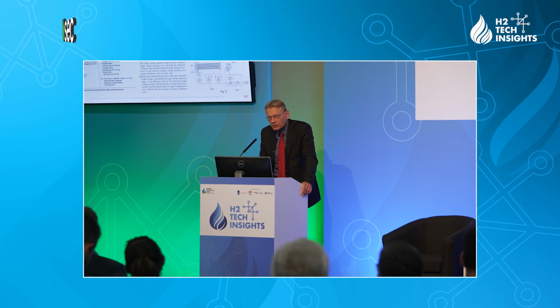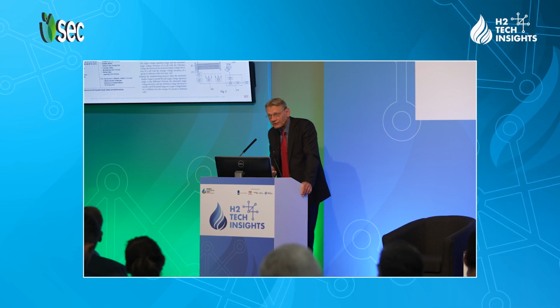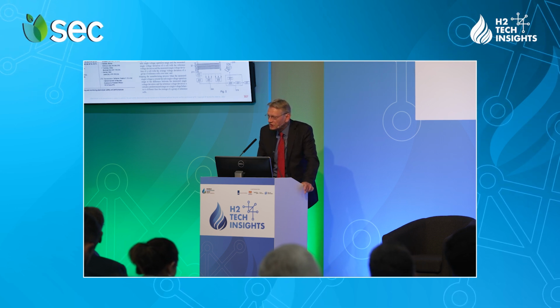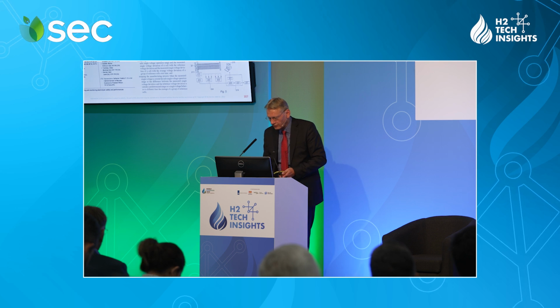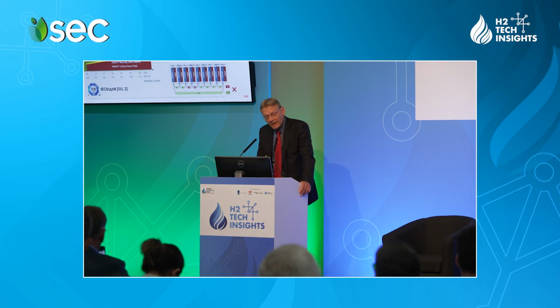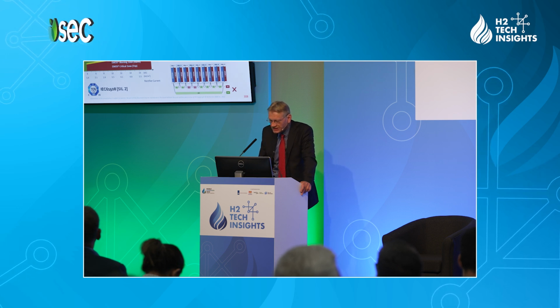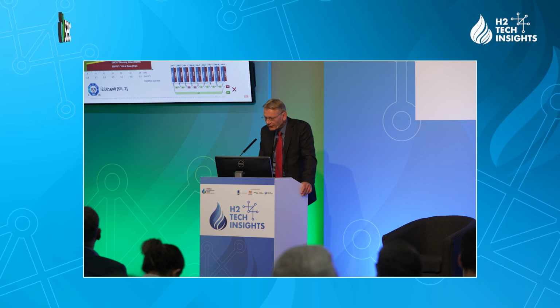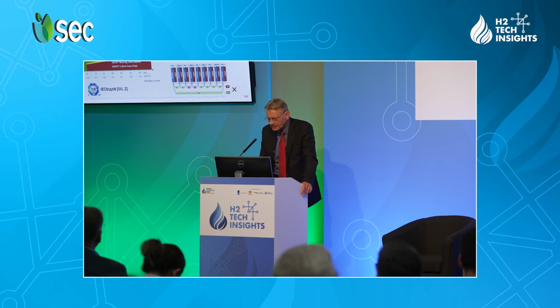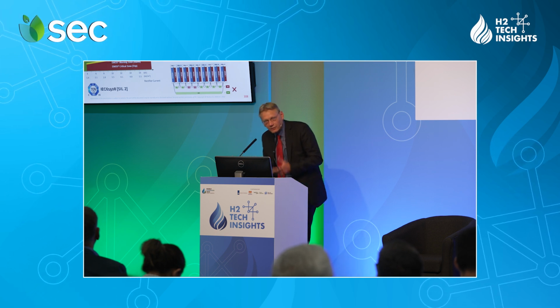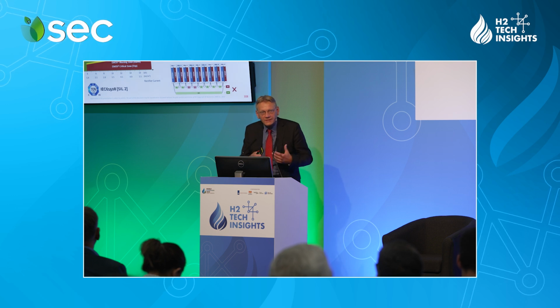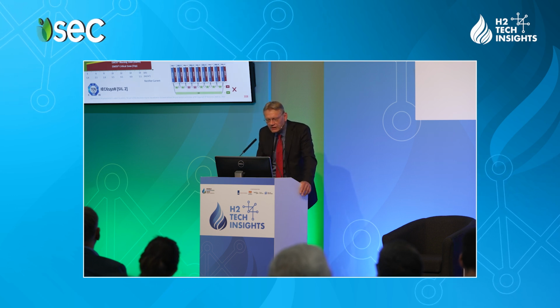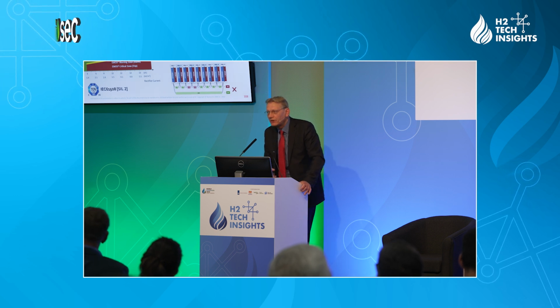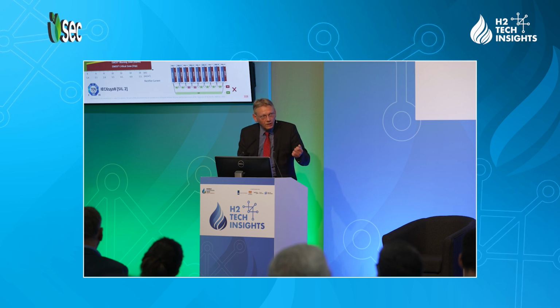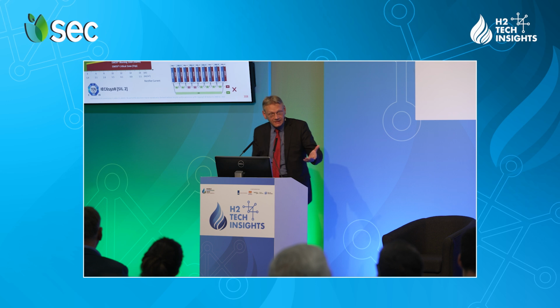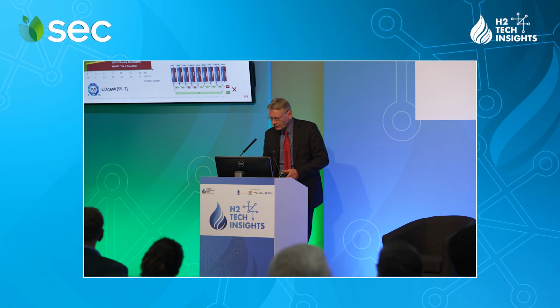And if you want to have a risk reduction according to SIL 2, safety integrity level 2, it's the only way to reach the target, which means you catch minimum 99 out of 100 incidents. To prevent false positive low voltage detection from a bad connection between cell and voltage measurement hardware, it's very important to have self-validation. So this is inbuilt. We are calculating the sum of individual cell voltages. We compare with the group voltage, because otherwise there will be no acceptance to install in a plant a low voltage trip. So you need this unique feature to avoid any false trips, because in a gigawatt factory, if you use the single cell voltage, you have 10,000s of copper connections between an AD converter and the cell. So you should not trip if there is only a loose cable.